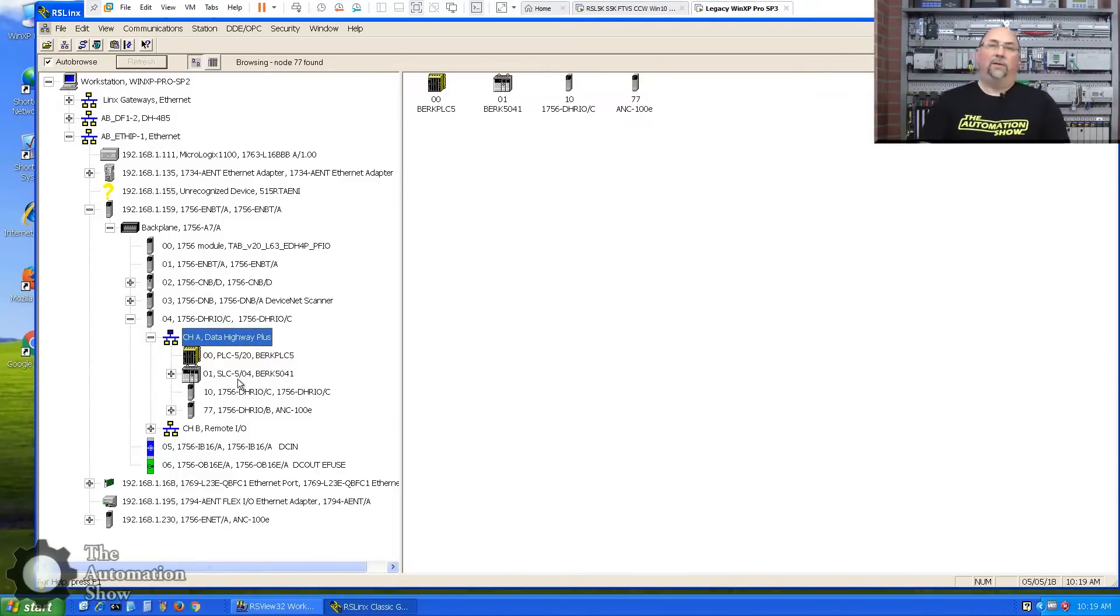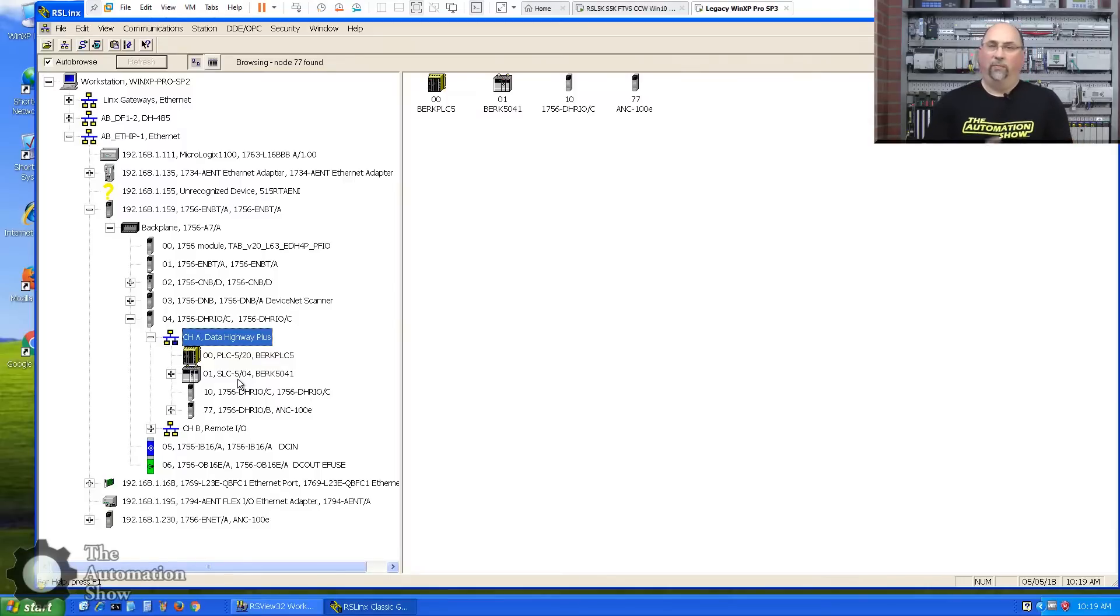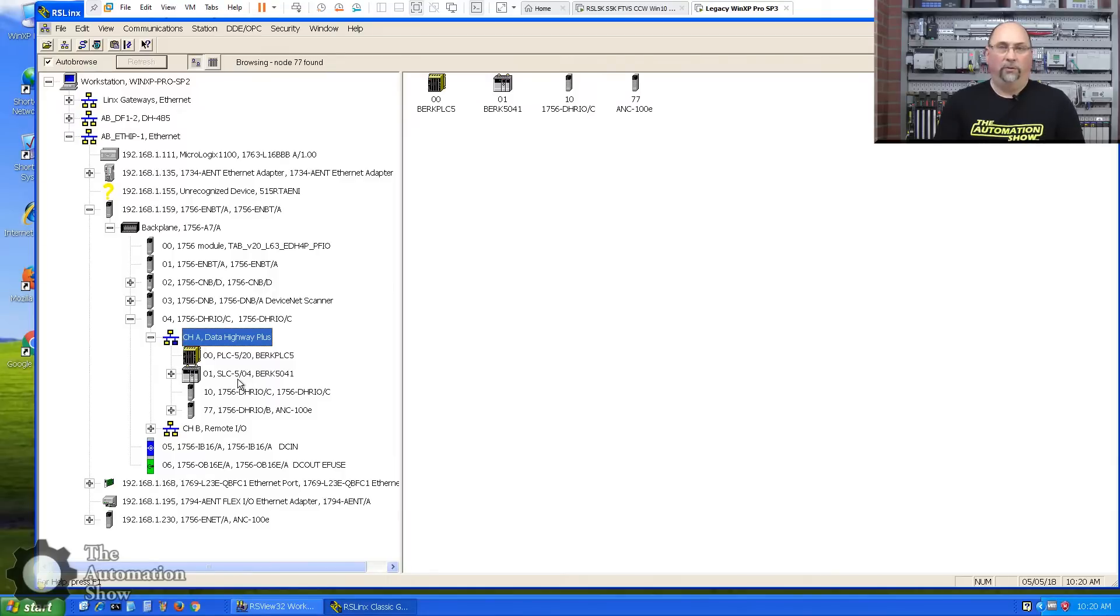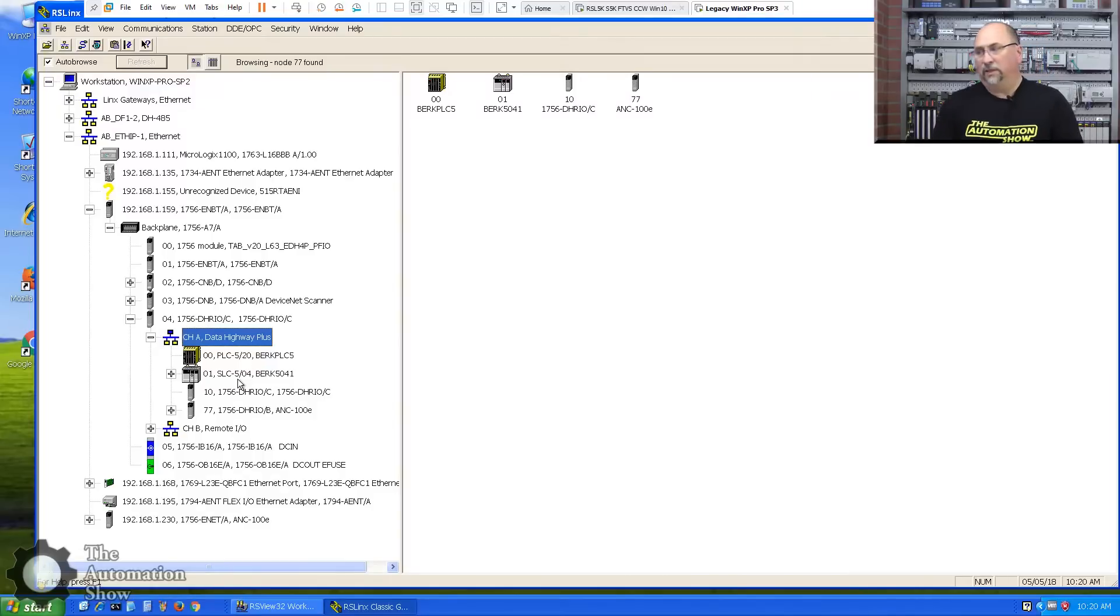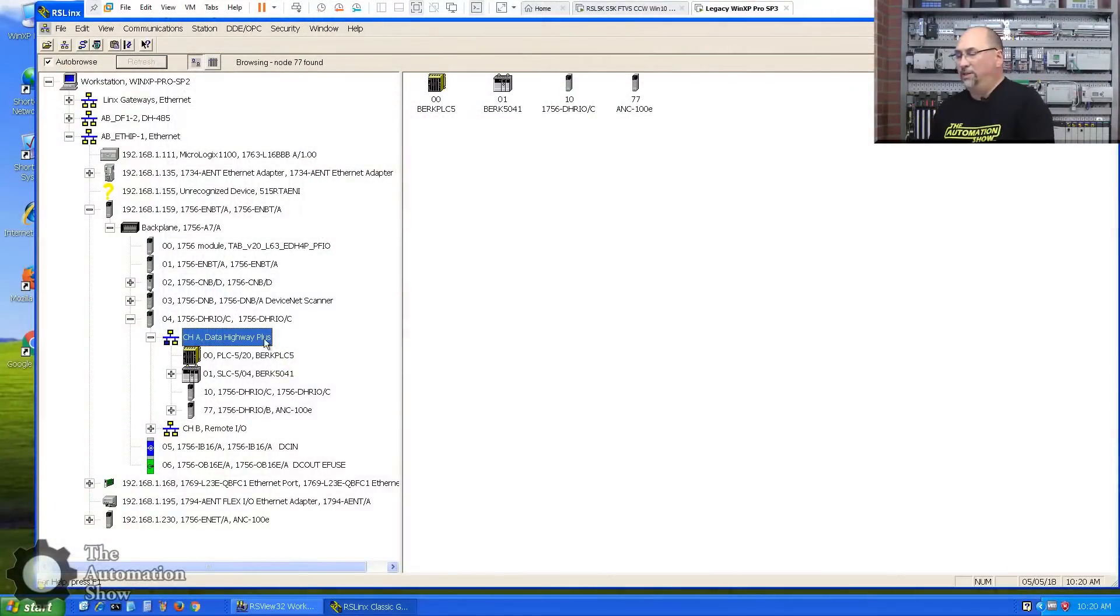So one of the things we have to do, because we're using a ControlLogix gateway here and not a KT card, KTXP, KTX card in the computer, is we're going to have to use OPC between RSView32 and RSLinx. Now this won't work if you have the demo version of RSView32, because without an activation for RSLinx Classic, the OPC doesn't work. So RSLinx Classic Lite is really designed just for use with RSLogix or Studio 5000.